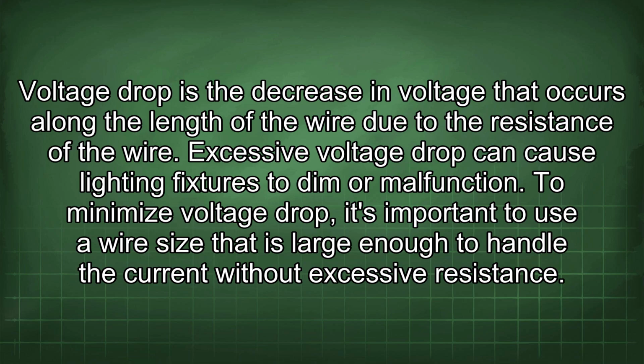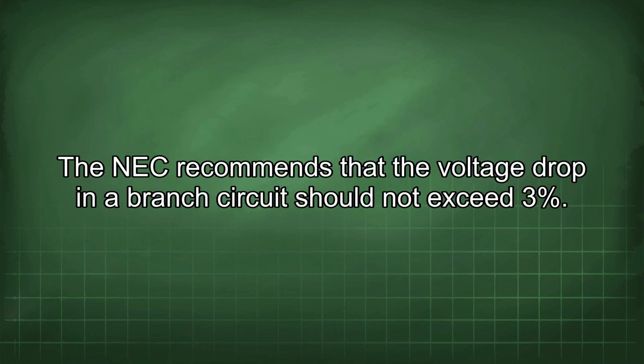Voltage drop is the decrease in voltage that occurs along the length of the wire due to the resistance of the wire. Excessive voltage drop can cause lighting fixtures to dim or malfunction. To minimize voltage drop, it's important to use a wire size that is large enough to handle the current without excessive resistance. The NEC recommends that the voltage drop in a branch circuit should not exceed 3%.